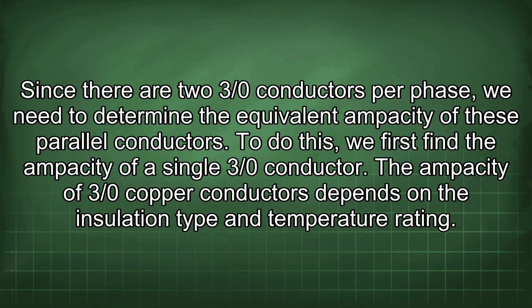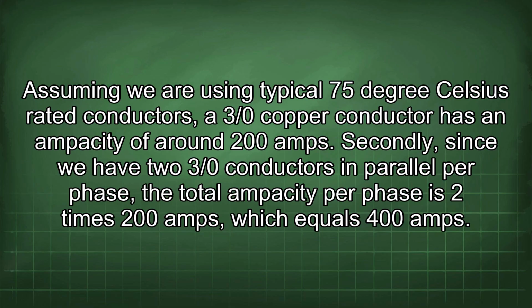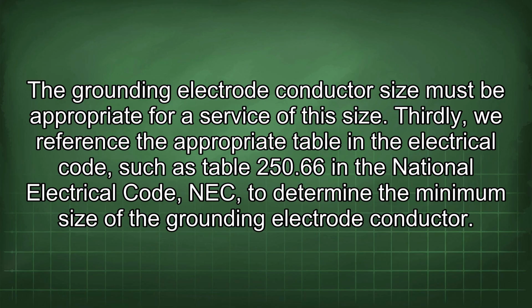To do this, we first find the ampacity of a single 3/0 conductor. The ampacity of 3/0 copper conductors depends on the insulation type and temperature rating. Assuming we are using typical 75 degrees Celsius rated conductors, a 3/0 copper conductor has an ampacity of around 200 amps. Secondly, since we have two 3/0 conductors in parallel per phase, the total ampacity per phase is 2 times 200 amps, which equals 400 amps. The grounding electrode conductor size must be appropriate for a service of this size.